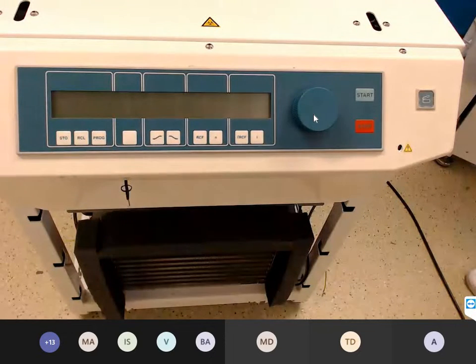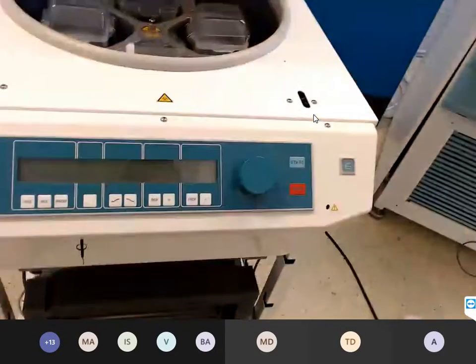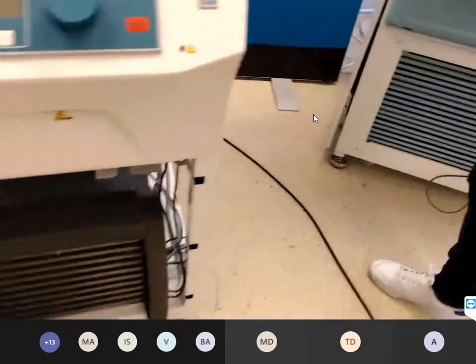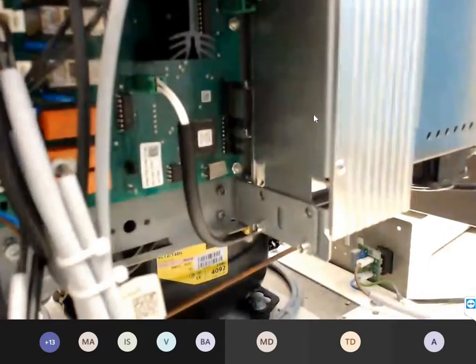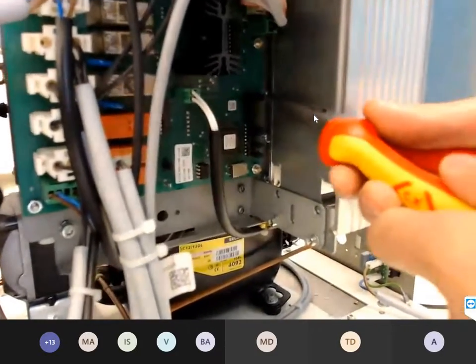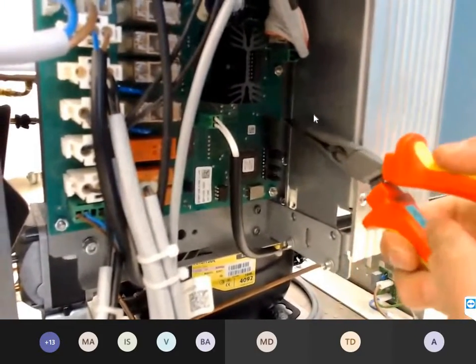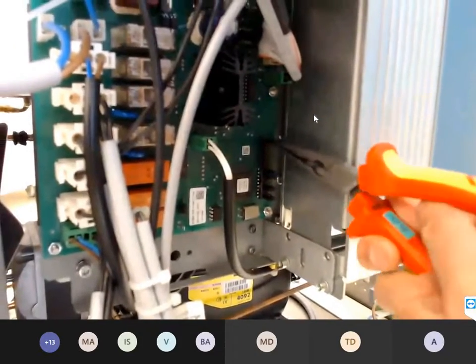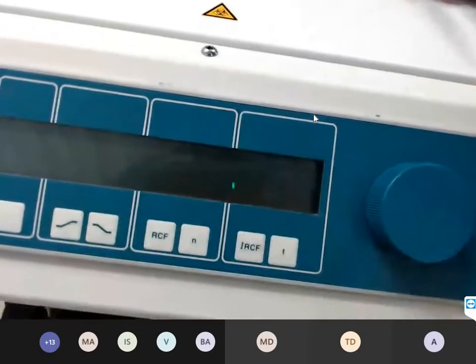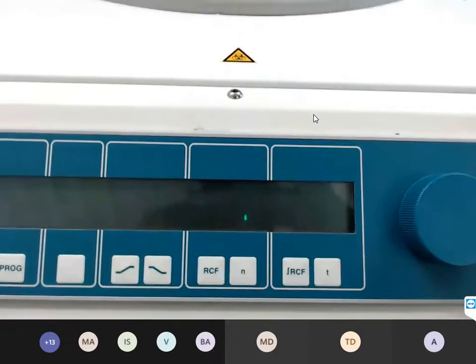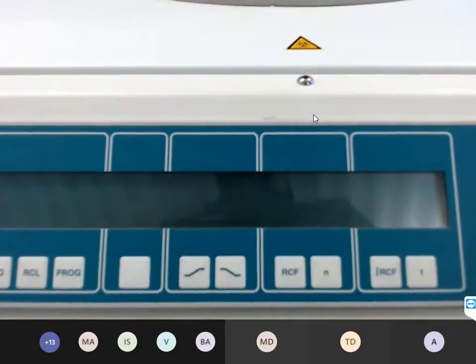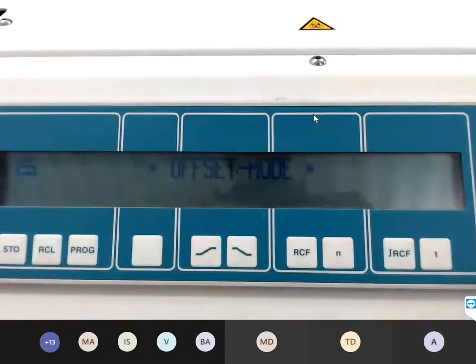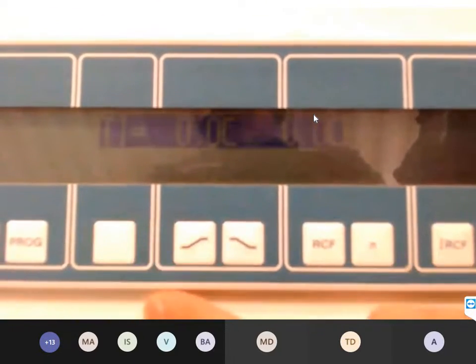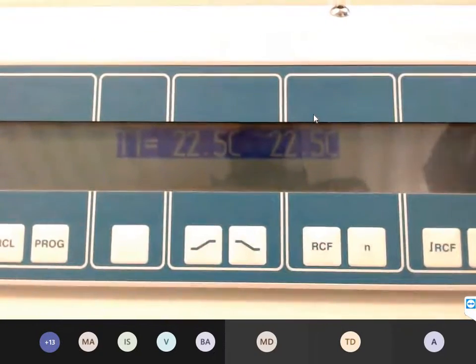For this, we have to change the position of the jumper here. We have here on the right side the electronic boards with the jumpers. This first jumper is for the settings. Plug it on B0. Switch on the device for access to the offset menu. Now we are in the offset mode. Press this key here, and then you can change the offset value.